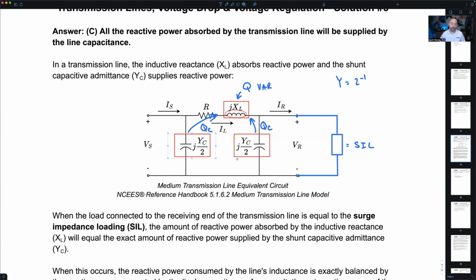Now, in real life, am I connecting two capacitors in parallel at the start sending and the end receiving side of my transmission line? Am I actually putting a big capacitor there? Or is this just what? This is just a model. The two capacitor symbols on your screen represent the naturally occurring capacitive characteristics of our transmission line, of the conductors between themselves and a little bit between the conductor and ground, where the conductors almost behave like two plates on a capacitor.